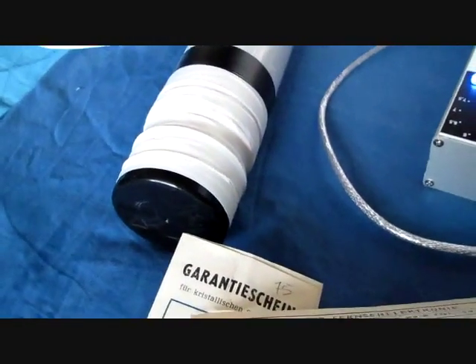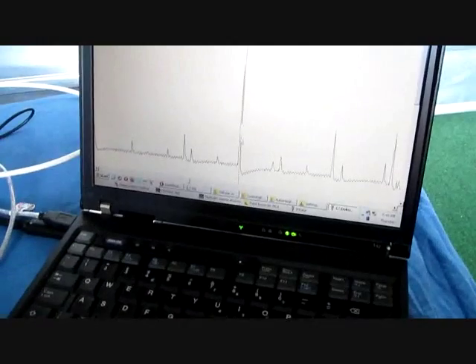With this detector we get a lot of ambient radiation, even when no radioactive source is near, because it's very sensitive. It's a large 2-inch crystal, as I said. So now we see we're getting these pulses. Now we're going to use the software.